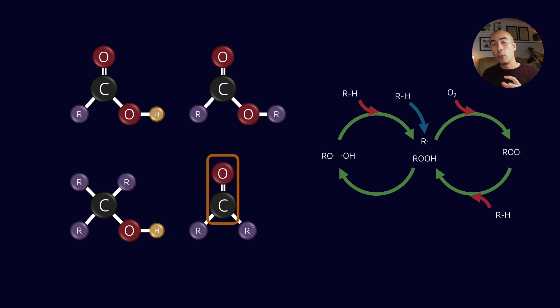So we can look for that specific bond, and the amount of those bonds that are present in the bulk oil will give us an indication of the oxidation.